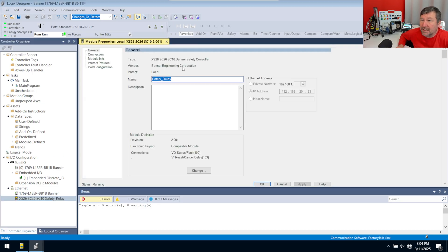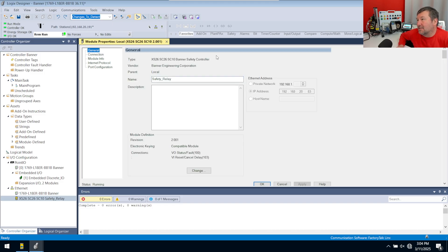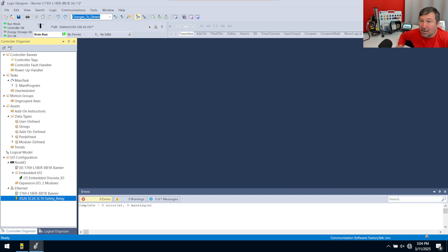If you see that yellow triangle, open it up and go to the Connection tab — it will tell you right there why it's not connecting. I'll say with 90% certainty it will be that you entered the wrong IP address. But if we've got that part sorted, now what we want to do is be able to reset this module over Ethernet.